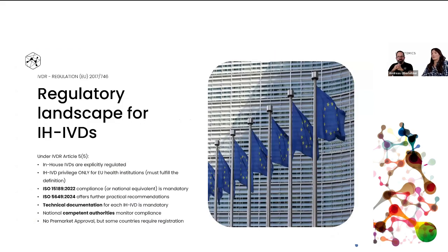So I would also like to talk about the regulatory landscape for the in-house IVD. So in general, the in-house IVDs are explicitly regulated. And as mentioned, the in-house IVD privilege is only applicable for a health institution within the EU. And it is also important to highlight that once you're manufacturing and using in-house IVDs, your health institution definitely needs to show the compliance to ISO 15189.